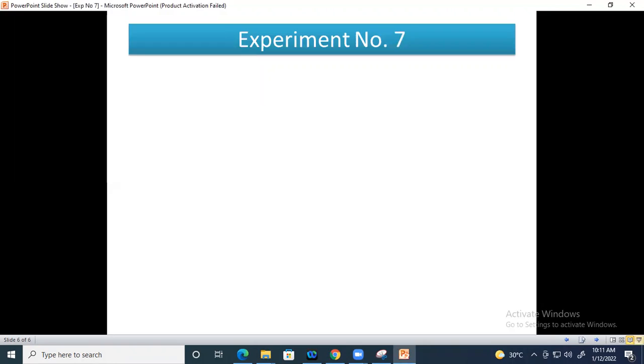Whenever we find efficiency at any load, these losses are used. The second test we performed is the short circuit test. By performing the SC test, we are able to calculate the equivalent circuit parameters referred to one side. So this equivalent parameter we calculate by performing SC test, like equivalent resistance referred to one side, either secondary or primary. Here we are referring to the secondary side, so we calculate equivalent resistance R02, equivalent reactance X02, and equivalent impedance Z02.